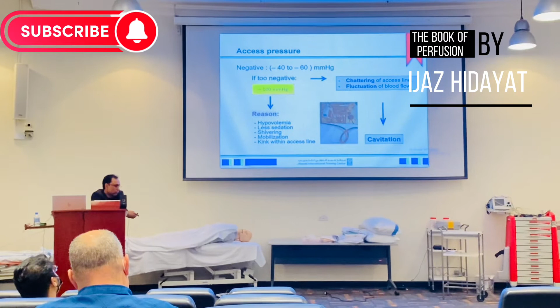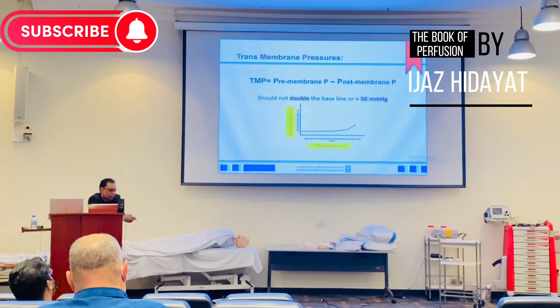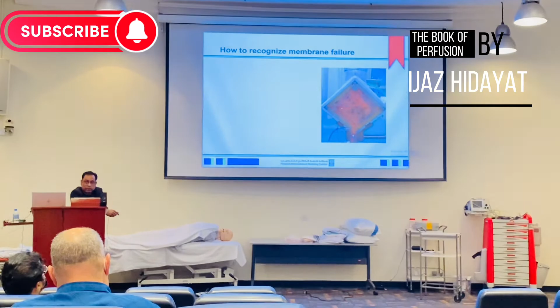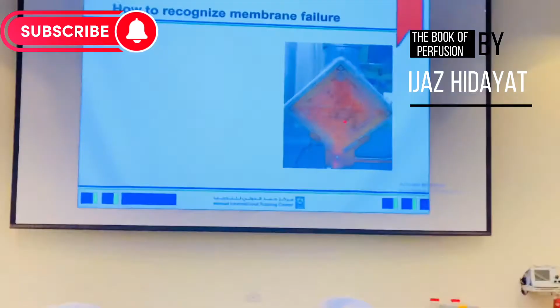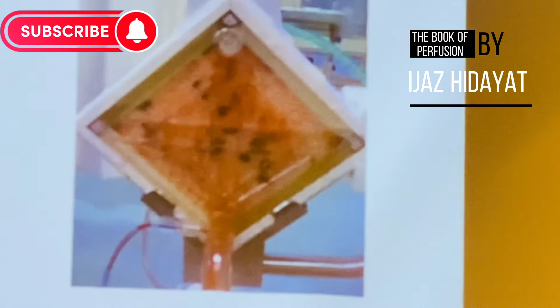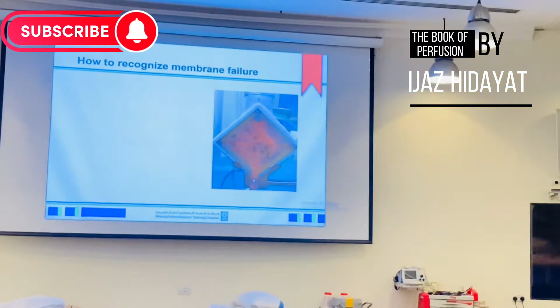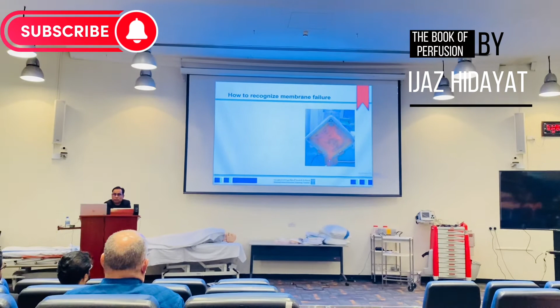So I will discuss: if your delta P is more than 50, you need to change your oxygenator, and then go with your gas transfer formula and equations. Okay? This is the reason for a delta P increase: resistance because of blocks. So you have the daily inspection, check your oxygenator and see if there are any clots. Normally, report if there is clot or fibrin formation in the oxygenator. It is going to relieve the failure of your oxygenator, or you need to change the oxygenator in an elective way, not in a volatile situation.